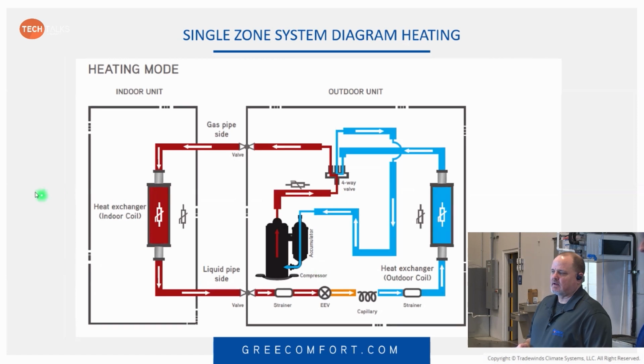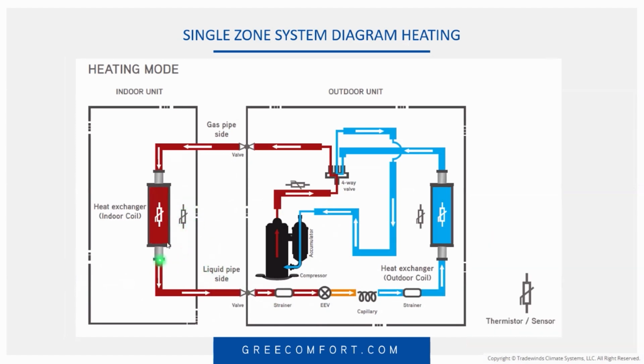In other words, what I'm getting at is you have that coil thermistor on the indoor unit, you have a coil thermistor on the outdoor coil, you have an indoor ambient thermistor, you have an outdoor ambient thermistor, and you also have the discharge thermistor. So the program in that board in that outdoor unit is looking at all that data. It's saying, okay, let me give you an example. Let's say I've got the indoor unit set to 75 degrees in heating mode. The indoor ambient is 65 degrees. I have a 10-degree demand for increasing the room temperature in that room.